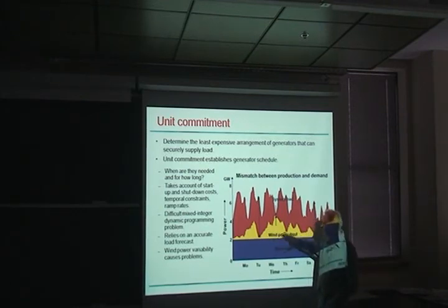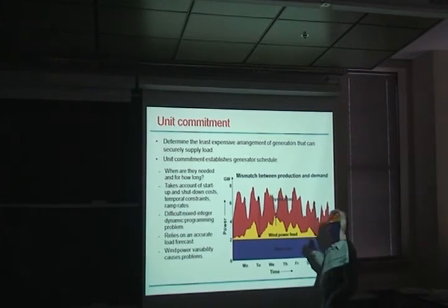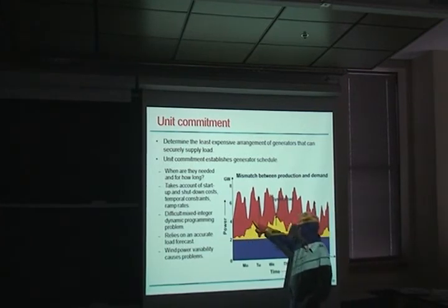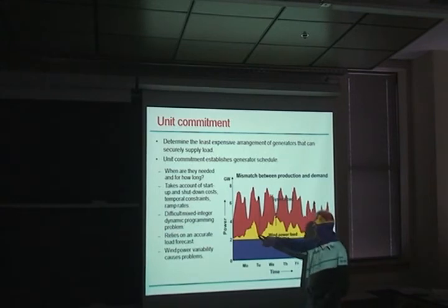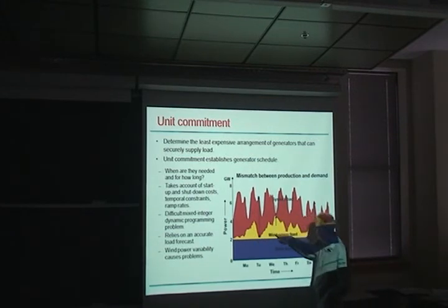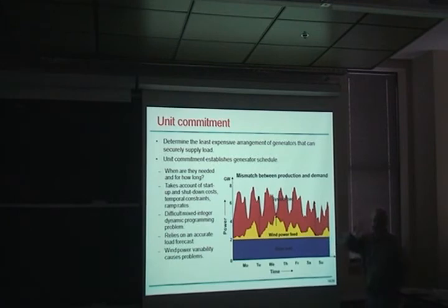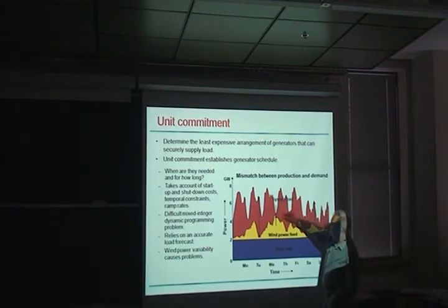If you look at wind, this is a fictitious example, but it's illustrative of how things really happen. You get this wind power that is varying depending on weather patterns, and it's often anti-correlated with the actual demand. And so you have periods like here where there's a lot of wind happening overnight, and so all the other generation is making up a tiny little difference there.